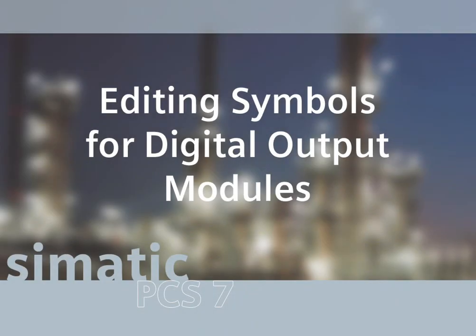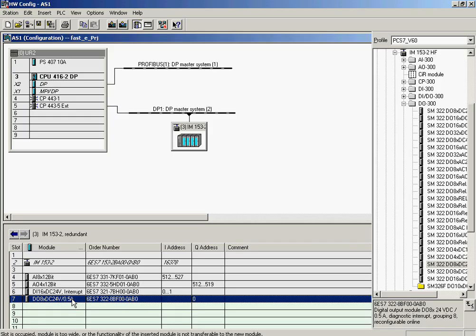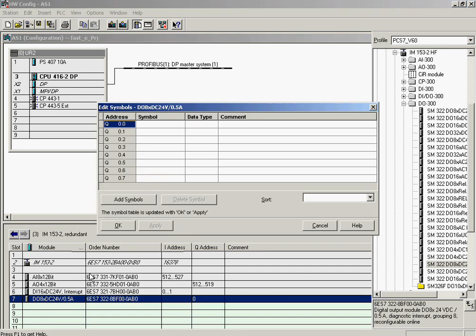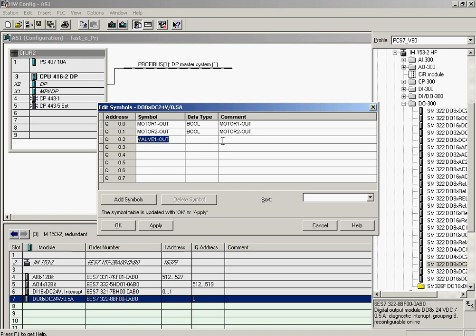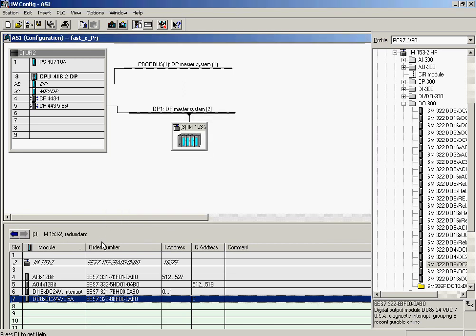The last step is to assign the symbolic addresses to the channels of the digital output module. The Edit Symbols dialog is opened. The symbol name for switching motor 1 ON/OFF is entered in the first line and comment column. The corresponding name for motor 2 is in the second line, the symbol name for opening or closing valve 1 in the third line, and the corresponding name for valve 2 in the fourth line. The dialog is completed by clicking OK. All required symbolic addressing has been defined.